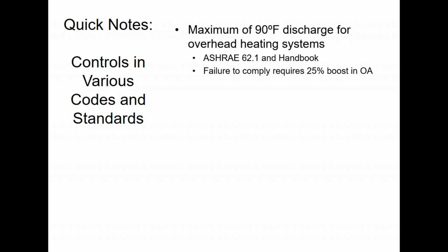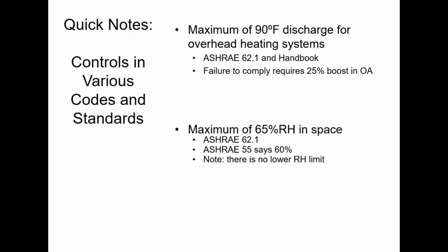But if you're doing a rooftop system, there's tons of rooftop systems that are out there way above 90 degrees. I see a lot of VAV boxes trying to maintain above 90 degrees. That's way, way too high. That means you're heating the space above 75, which doesn't make sense. If you heat the air too much, it stays up at the ceiling, as you might guess, and then the ventilation air does not end up going down into the space. So you have both a comfort problem and a ventilation problem.